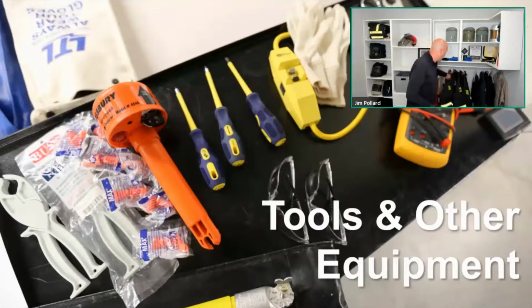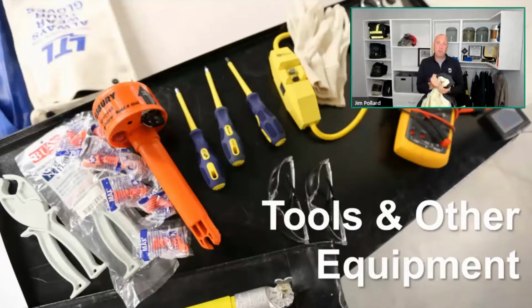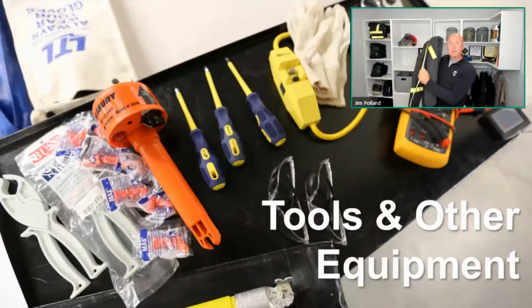I want to show you an example of a rescue device that's built into your suit. If you have a rescue stick, which is typically a 6-foot insulated stick with a shepherd's hook on the end, an alternative to that is now an escape strap. I'll just demonstrate with Oberon's escape strap here. On the inside of the suit, we've sewn in a Kevlar strap. It's a Kevlar rope, and it's sewn in so it goes around the worker's shoulders. In the event you have to pull a worker or drag them to safety, this will be very effective. On the back, the rope just hangs out in this little pocket, and then we can leave it out there, so it extends out the back of the coat about 10 feet.